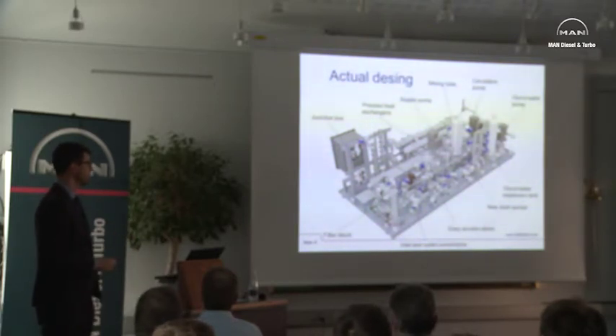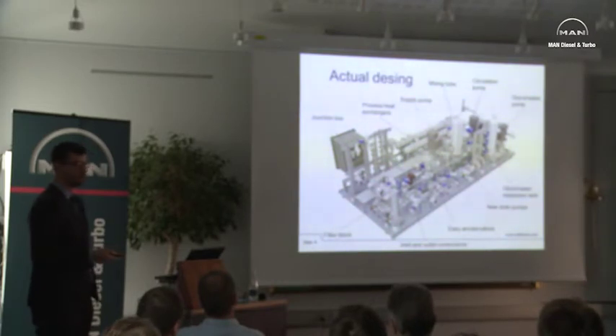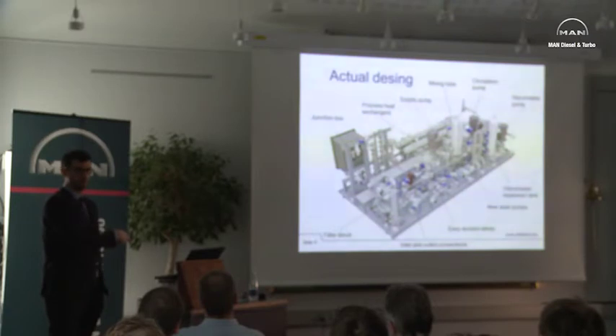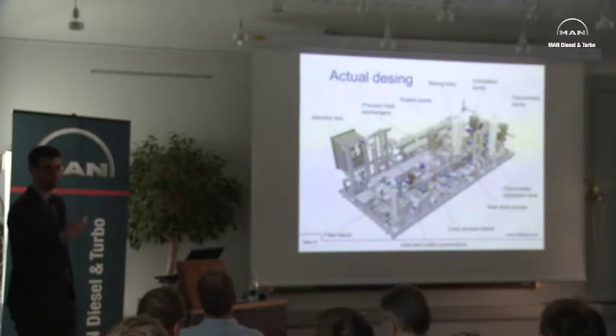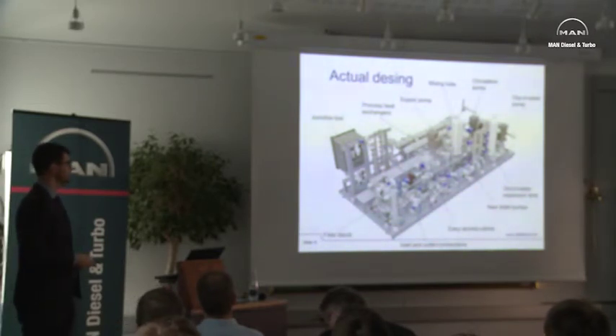So how to deal with vapors in automatic filtration, whatever kind of style you want to adopt in automatic cleaning of the basket filters. So what we ended up with so far was to use a double block and bleed installation. Therefore, you can switch to the standby filtering element, and then, in the new generation, you manually purge from the side the candle or the insert that was in process up to that moment, and then you can safely open the chamber, take it out, replace it, and restore a standby filtering element without the need to stop the system.